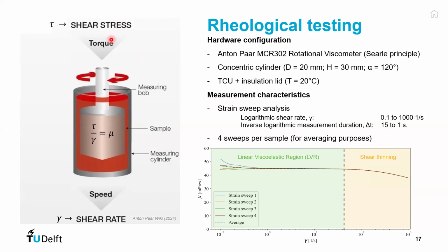If we look at this picture over here, what we are doing is trying to rotate our measuring bob, that's the pointy part of the figure here, inside our fluid at a predefined speed. That means that the fluid is experiencing a certain shear rate. Then we are measuring the required torque in order to rotate this bob at the required speed. And because we know very accurately the dimensions of our measuring bob, we can then also calculate the shear stress. Now, if we have the shear stress and we have the shear rate, we can use this relationship in order to calculate the dynamic viscosity of the fluid.